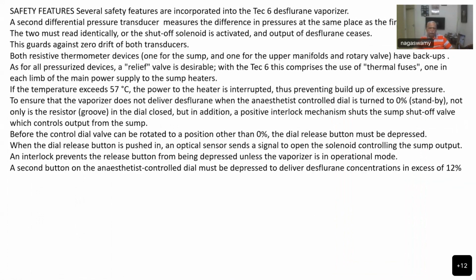And there are several safety features incorporated. A second differential pressure transducer measures the differential pressure in the same place as the first transducer, and the two must read identically or the shut-off solenoid valve is activated and the output of desflurane ceases. So in the earlier picture I showed you, there are two different pressure transducers present, and they should read the pressures identically. Otherwise, the shut-off valve, which is just outside the sump outlet, will shut off automatically. This guards against zero drift of both transducers. So this is very important.